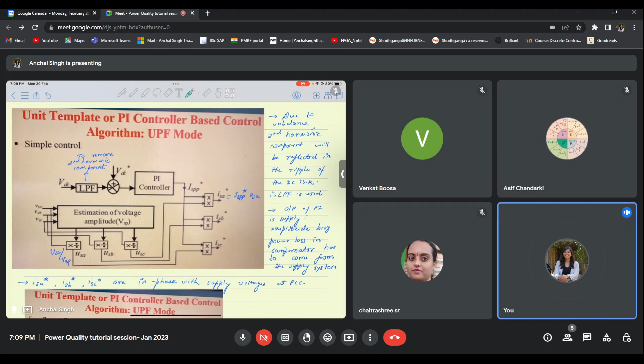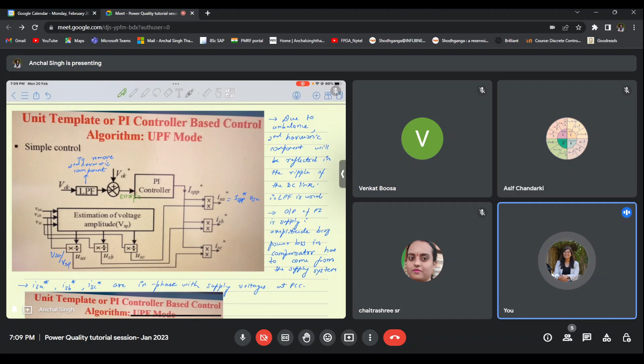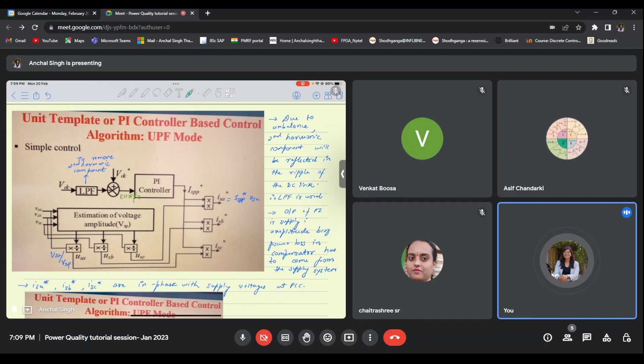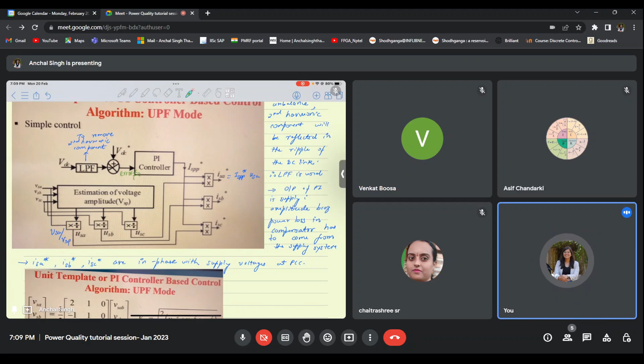So the capacitor will give its energy, and what will happen is its DC link voltage will come down. The moment the DC link voltage comes down, this circuit will start operating. This error which is coming here will no longer be zero. It will become non-zero, and then this controller will operate and give references. Based on these references, I will later compare them with the actual supply currents, and using those current controllers, I will generate the pulse width modulated signals for the switches to operate, the gate pulses. Whenever there is a switch, you need to give it an on-off signal. This on-off signal is called the gating pulse.